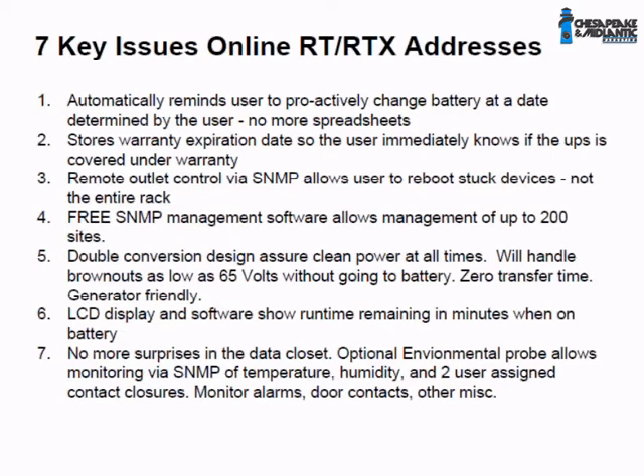With double conversion online, the RT and RTX can handle brownouts as low as 65 volts. For example, an APC SmartUPS line interactive unit will switch to battery at about 92 volts. So there's a very significant difference in power quality.